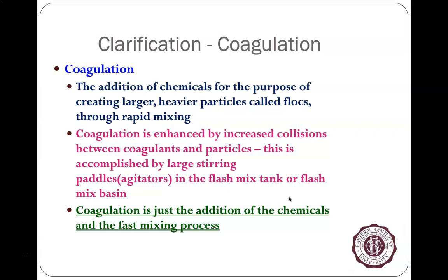After we have pulled in the water, we will then do coagulation. Coagulation is a step whereby we add the chemicals, a coagulant, and it produces these larger things called flocs. So you add the chemical, and it produces flocs, which are these little round globs of usually mostly sediment that are able to be heavy enough and they stick together enough that they then settle out when we slow the water down. Before we do sedimentation, we have to do coagulation.